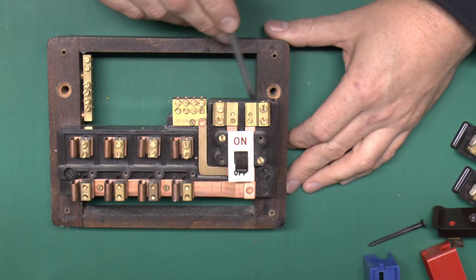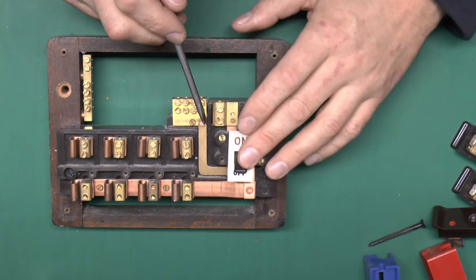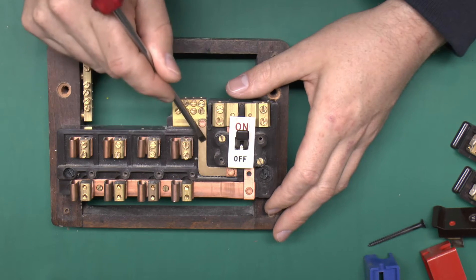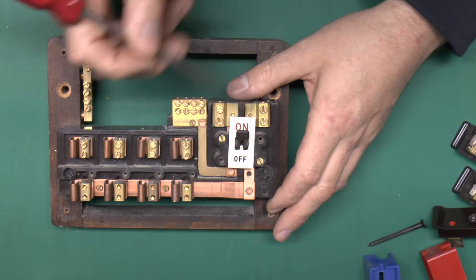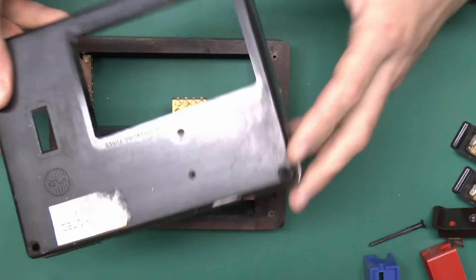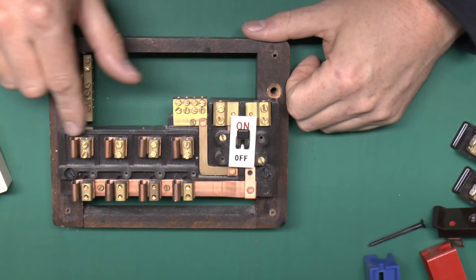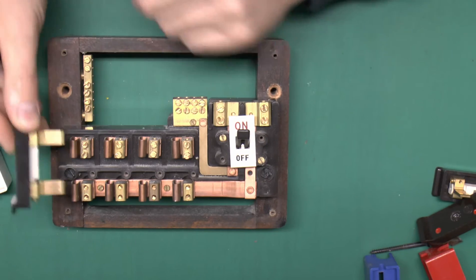Inside we've got the two terminals for the incoming supply — the line on this side and neutral there. There are usually some plastic covers which fit over here because these are going to be live regardless of the position of the switch; they're missing from this one. It's a double-pole switch, on in the up position and off in the down position. The neutral goes straight through to this bar and up to the neutral block — four terminal holes, one for each circuit. The line goes through to the bottom via a copper strap to those four pieces along the bottom. With the switch on and the fused carriers removed, all of that is going to be live — hence why you don't want to be taking these out without turning the switch off first. The top ones are simply individually isolated, the connection made with the fuse, and the outgoing circuits connect at the top.